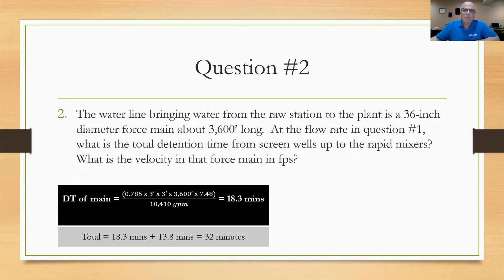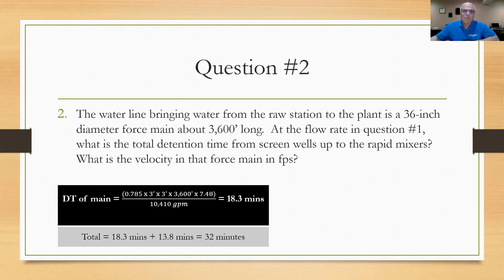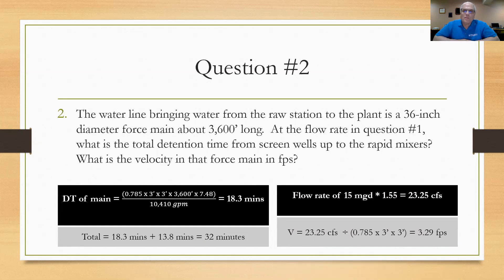The second part of question two asks for the velocity in the force main in feet per second. Engineers typically design water mains with a velocity between one and five feet per second. To calculate velocity, we use V = Q/A. First, convert 15 MGD to cubic feet per second by multiplying by 1.55, giving 23.25 cfs. Then divide by the cross-sectional area of the 36-inch main: 0.785 times 3 squared. The result is 3.29 feet per second — right in the design ballpark.